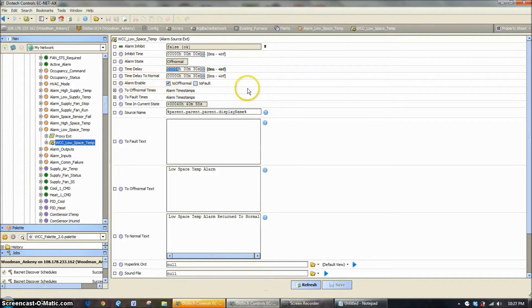Time delay to normal is after it's gone back to normal — how long do you want before it resets and starts over again? You'd want to have a fairly small time there, because once it goes to normal, it seems strange if you put the building or room to normal and then the alarm doesn't clear for a half an hour. So we try to keep that short, but the time delay to go into alarm should be a lot longer.